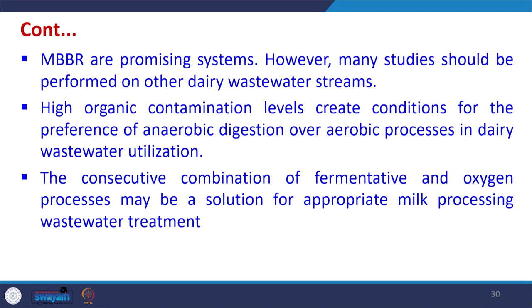MBBR is a promising system, and SBR can also be used, though more studies on MBBR are still required. High organic contamination levels create conditions favoring anaerobic digestion over aerobic treatment, so anaerobic processes or systems are preferred for dairy wastewater. A combination of fermentative and aerobic processes may be a solution for appropriate milk processing wastewater treatment — anaerobic first followed by aerobic — to fully treat the wastewater and achieve the minimum standards prescribed by the government.